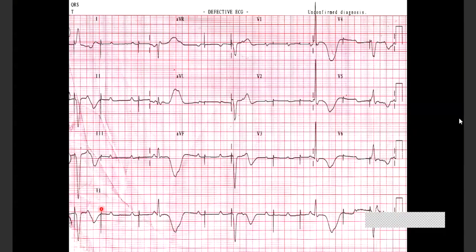So you're seeing more into it. Loss of capture could mean there's a lead problem or a battery problem. In a lead problem, the lead doesn't allow the current to flow across it to the ventricle. In a battery problem, the lead is normal, but the battery doesn't generate enough voltage for it to generate a capture. So here, the loss of capture seems to be secondary to a battery depletion, because the rate is irregular, and that's why there's loss of capture. And the capture is intermittent. Sometimes you have capture, sometimes you have no capture.